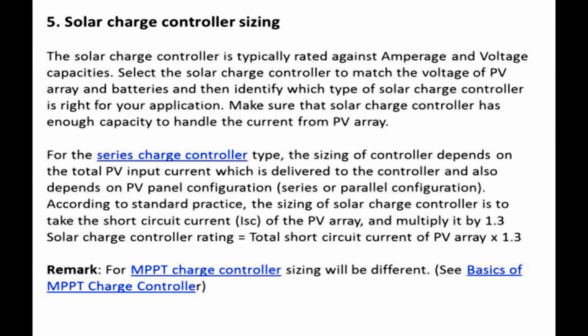Step 5: Solar charge controller sizing. The solar charge controller is typically rated against amperage and voltage capacities. Select the controller to match the voltage of the PV array and batteries, then identify which type is right for your application. Ensure the charge controller has enough capacity to handle the current from the PV array. For series charge controller types, sizing depends on the total PV input current delivered to the controller and the PV panel configuration — series or parallel.